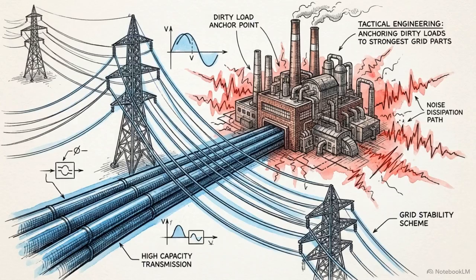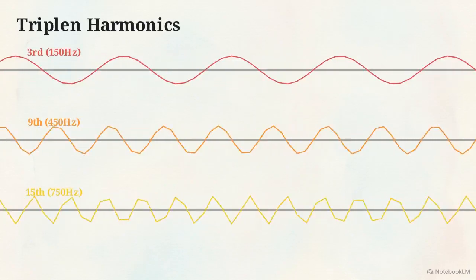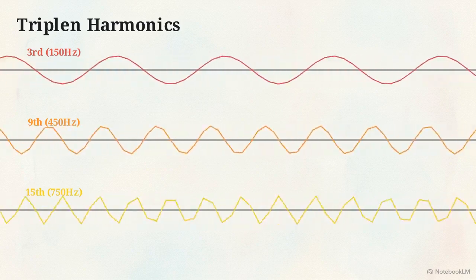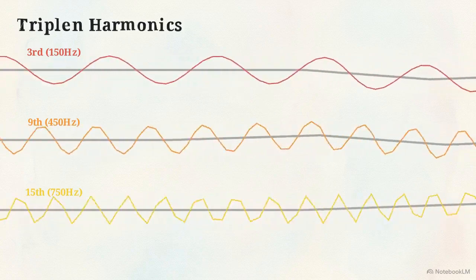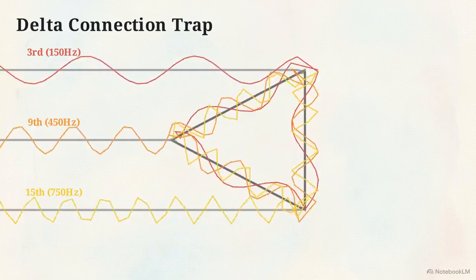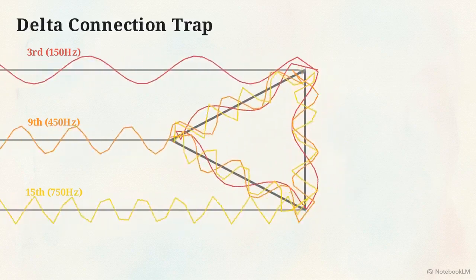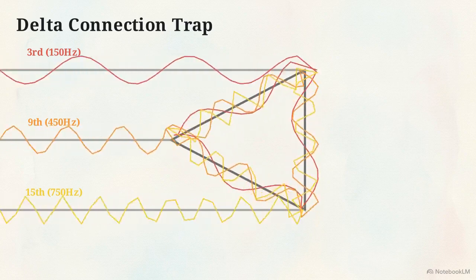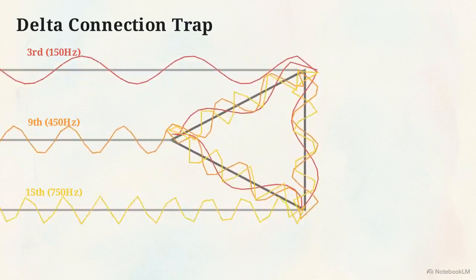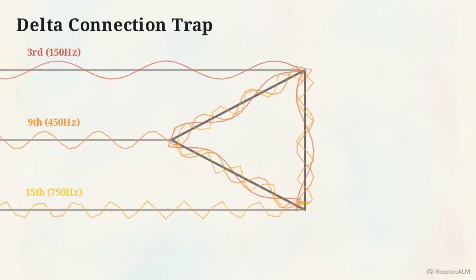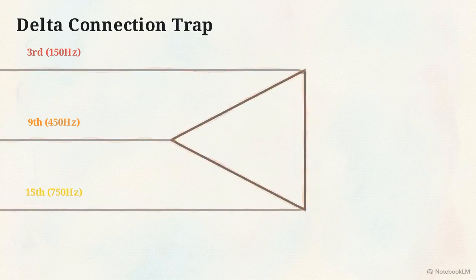Anchoring noisy industrial loads to the thickest, strongest parts of the grid is the first critical tactic used to contain the chaos. Engineers also use geometric traps to catch triplen harmonics, the 3rd, 9th, and 15th multiples of the base frequency. They use the delta connection, wiring transformers so internal circuits form a closed triangular loop. This geometric shape acts as a trap. The chaotic triplen frequencies enter the triangle but cannot exit. Circulating infinitely inside, they cancel out and safely dissipate as heat.